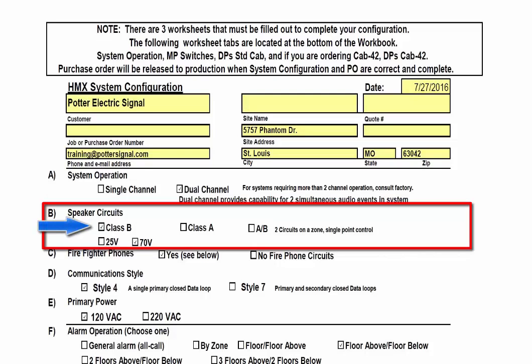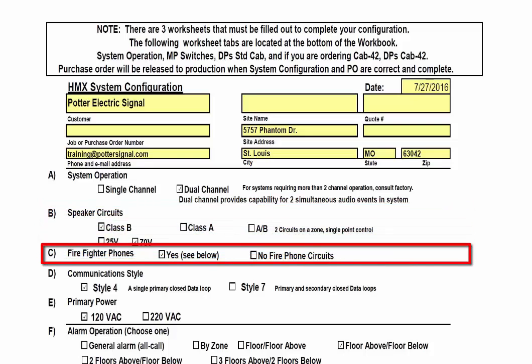After determining the wiring scheme for the circuit, you will need to choose whether it will be a 25-volt or 70-volt circuit. Firefighter phones are optional. If your system includes fire phones, then select Yes. Note that while up to five phones can operate simultaneously on a single phone circuit, party-line service is not available.